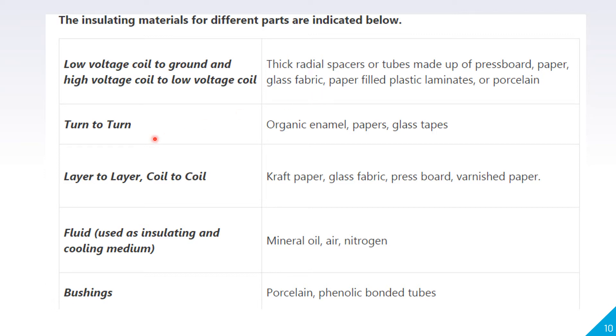Between one turn and another, the insulation used is organic enamel, paper, and glass tape. Layer or coil-to-coil insulation is provided by Kraft paper, glass fabric, pressboard, and varnish paper. The insulating oil used in a transformer is mineral oil, and the gases that can be used are air and nitrogen. Bushings are generally made of porcelain.